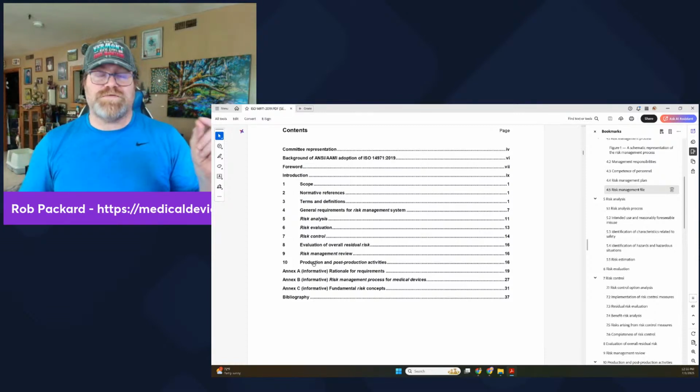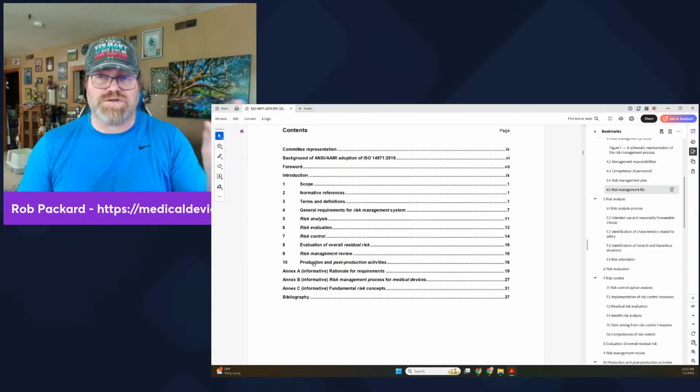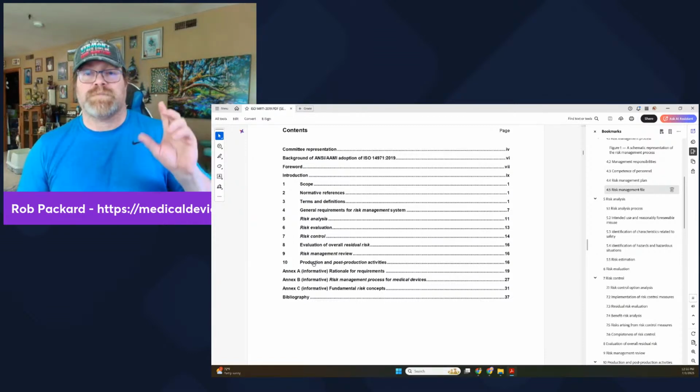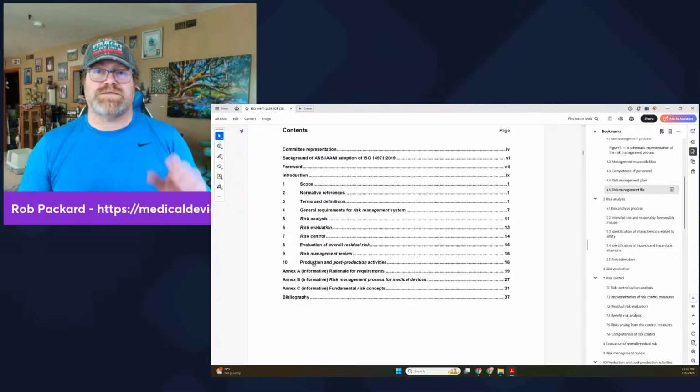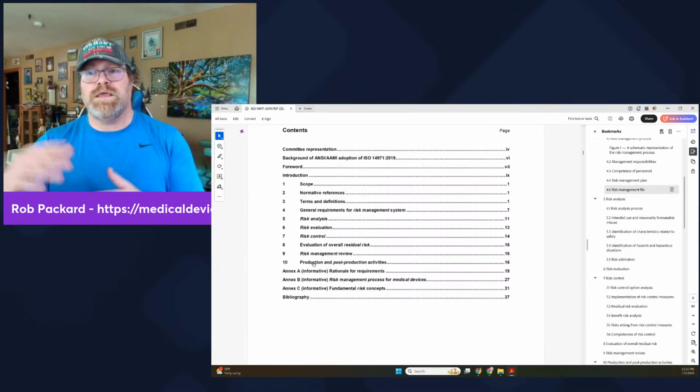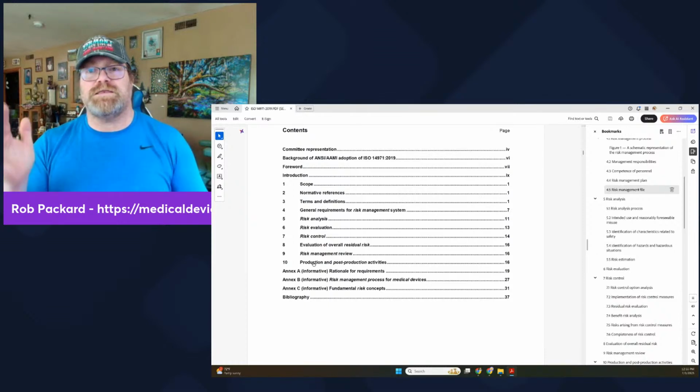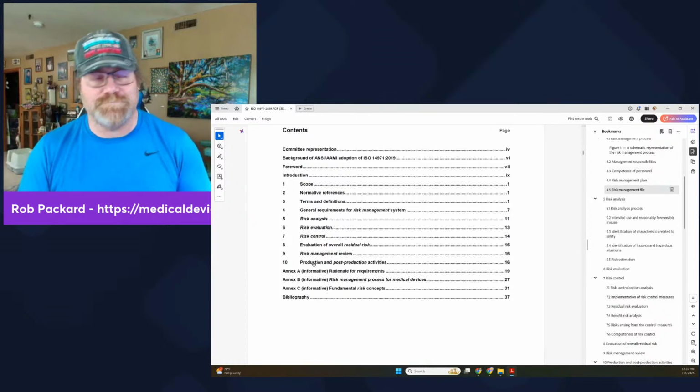So when did the hazard analysis occur? That was probably when you were defining what your design inputs were in your hazards. That's early in your process. Planning went with design planning. Hazards went with design requirements or inputs, and then probably the risk evaluation and risk analysis, risk evaluation, risk controls. Those were all during development. And once you've finalized and implemented, now you are ready for V&V testing.